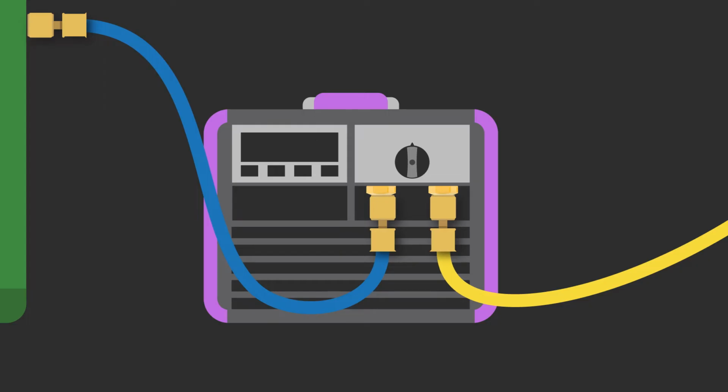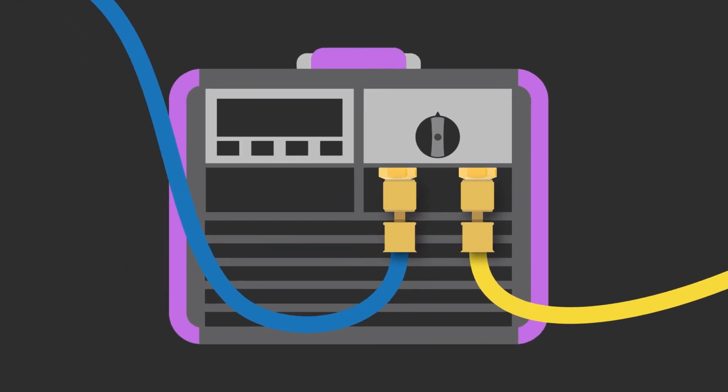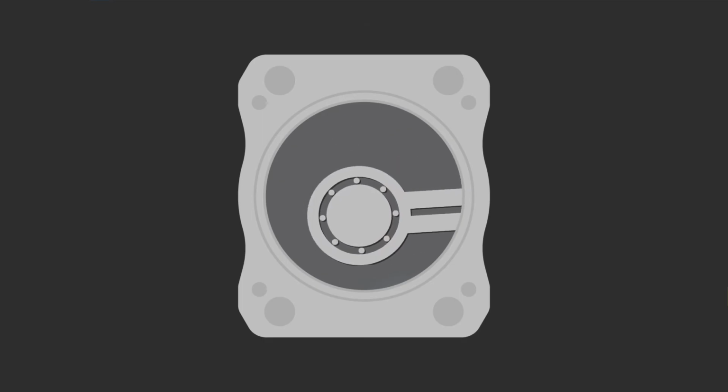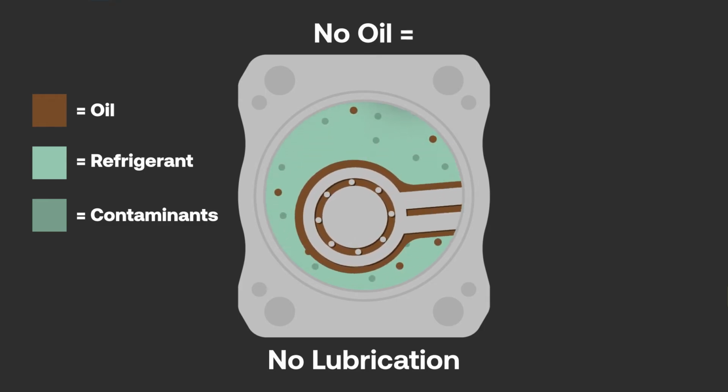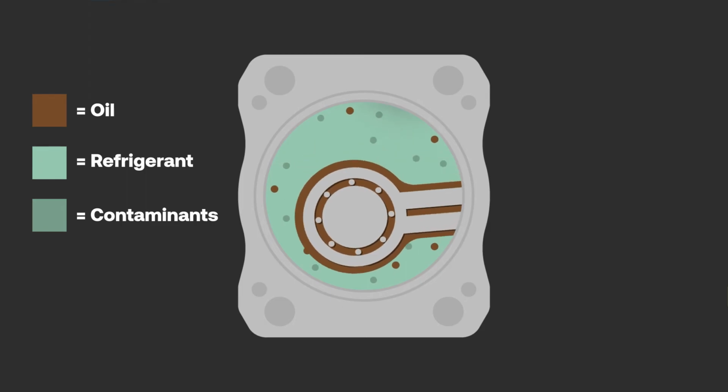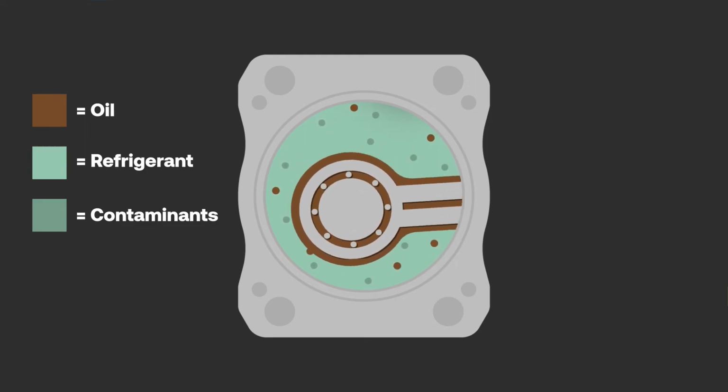In the 1990s, recovery machine manufacturers started to develop machines with oil-less compressors. These machines don't have an oil sump, but still require oil to lubricate rotating components. To get the oil needed for lubrication, some oil-less compressor recovery machines utilize a design known as a refrigerant-flooded crankcase. This design relies on system compressor oil trapped in the recovered refrigerant to enter the crankcase for lubrication. The downside to this design is the potential to flush the compressor bearings of any lubricating oils when pumping virgin refrigerant. This stripping of lubrication can lead to early failure of the bearings and possible cross-contamination.